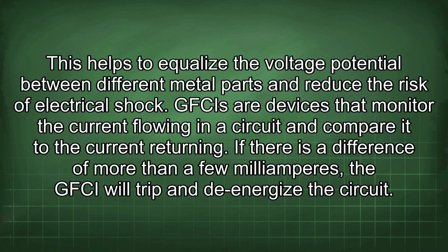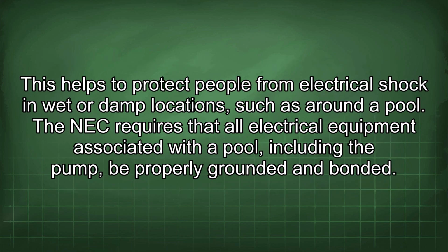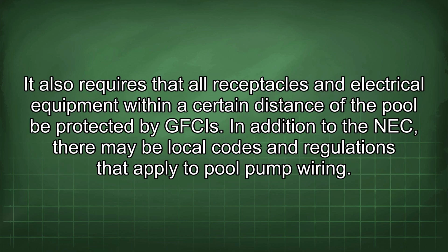GFCIs are devices that monitor the current flowing in a circuit and compare it to the current returning. If there is a difference of more than a few milliamperes, the GFCI will trip and de-energize the circuit. This helps to protect people from electrical shock in wet or damp locations, such as around a pool. The NEC requires that all electrical equipment associated with a pool, including the pump, be properly grounded and bonded. It also requires that all receptacles and electrical equipment within a certain distance of the pool be protected by GFCIs.